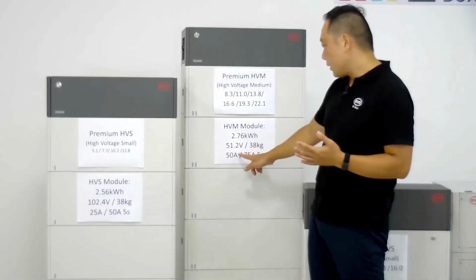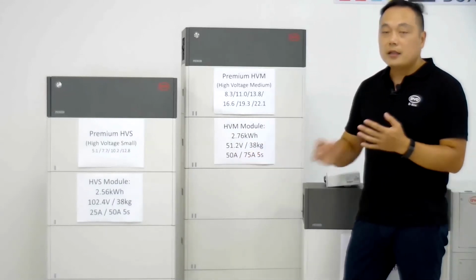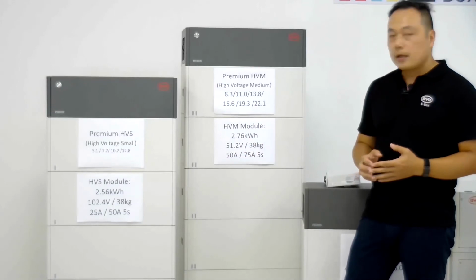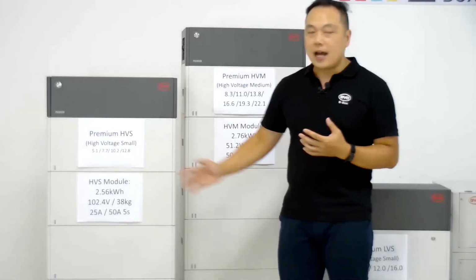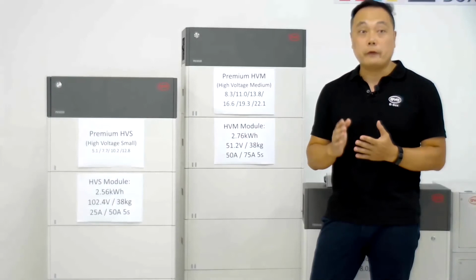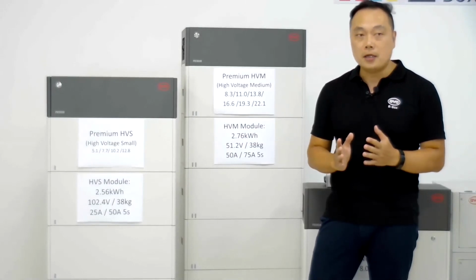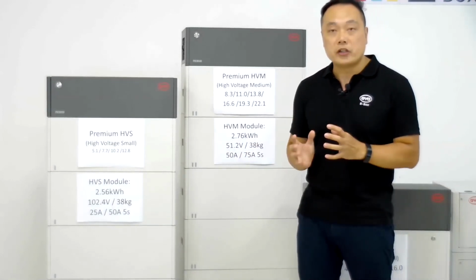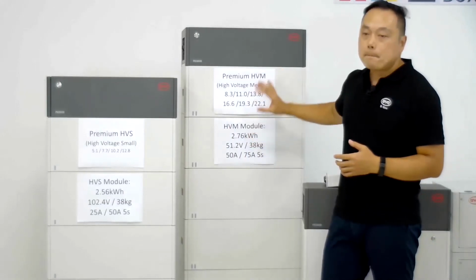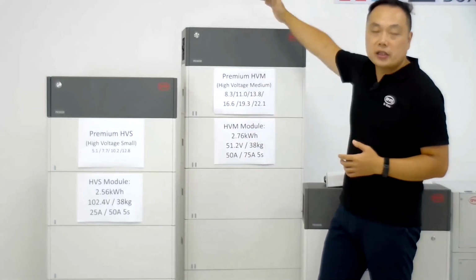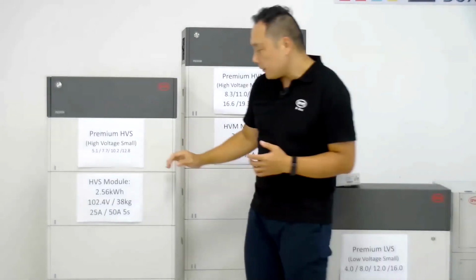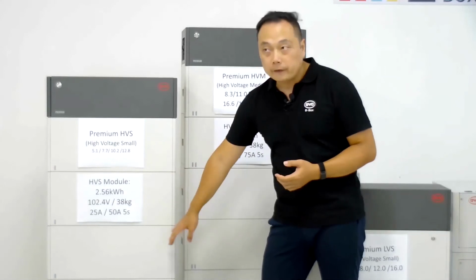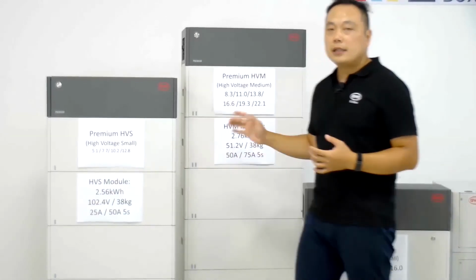But remember, this current is limited by the inverter, right? So which means if you need high backup power, like with the Fronius Gen 24, it can output 9 kilowatts backup power, then the current is limited, which means you need a high voltage to achieve that backup power, right? Which means if you have 8 battery modules of HVM in a stack, you can achieve that power output. Or alternatively, you can use 4 or 5 of the HVS, because for each module, the voltage is double that of the HVM. That's why we designed HVS and HVM.